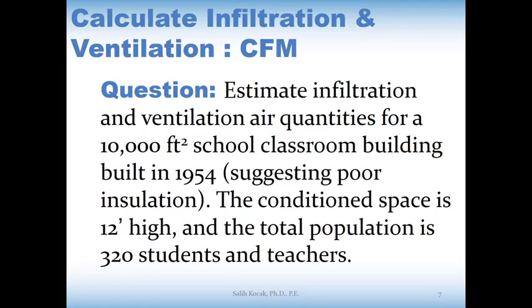The question tells us to estimate the infiltration and ventilation air quantities for a 10,000 square feet school classroom building built in 1954. The year is telling us that there was not good insulation at that time, or the insulation is not as good as in our time right now. That's why we are going to think about poor insulation conditions.